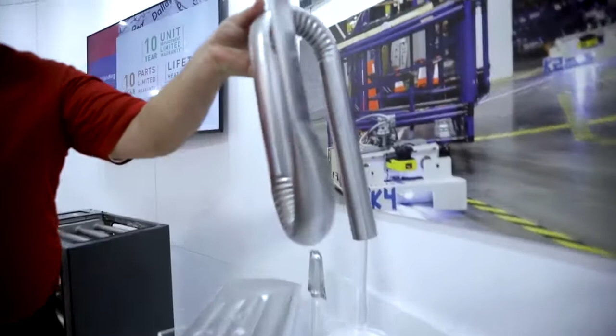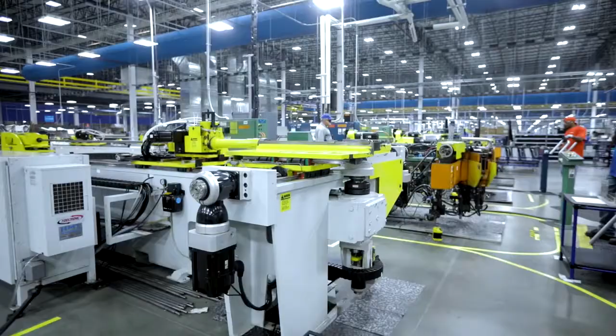That's exactly right, John, and it's these type of bends that make it more efficient? That's right. You see here on the inside diameter, we wrinkle the tube before we bend it. What that allows is for less thinning of the outside diameter, but it also, as the gas moves through this tube, makes the gas more turbulent, which increases the efficiency of the heat transfer in this particular technology.